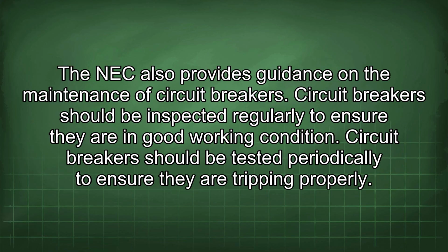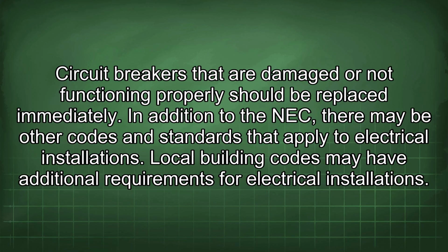The NEC also provides guidance on the maintenance of circuit breakers. Circuit breakers should be inspected regularly to ensure they are in good working condition. Circuit breakers should be tested periodically to ensure they are tripping properly. Circuit breakers that are damaged or not functioning properly should be replaced immediately.